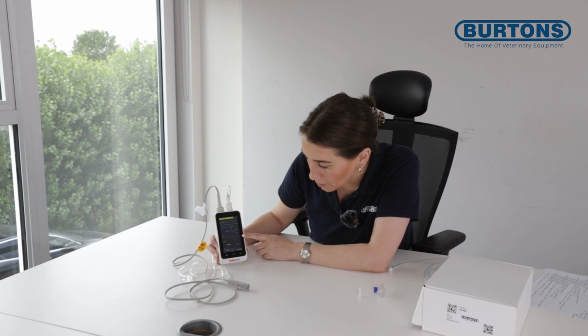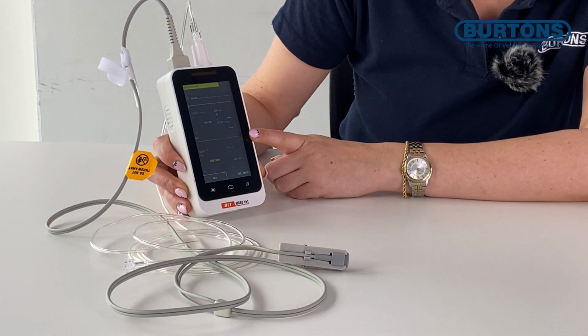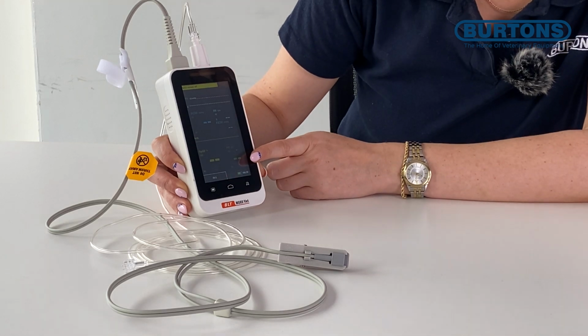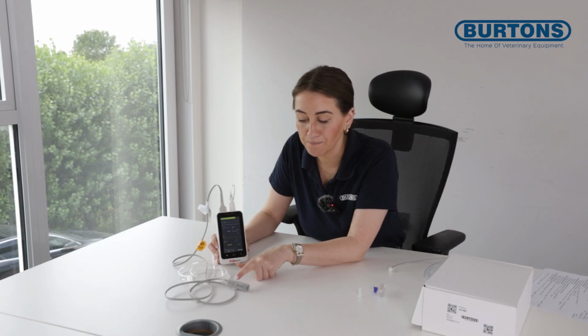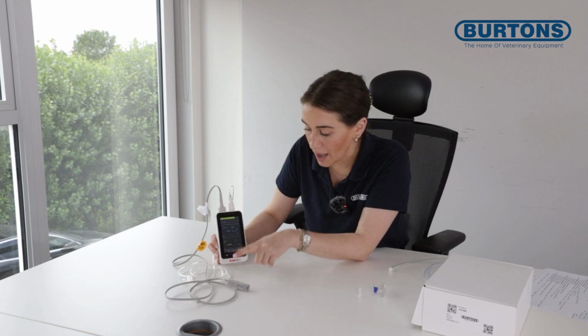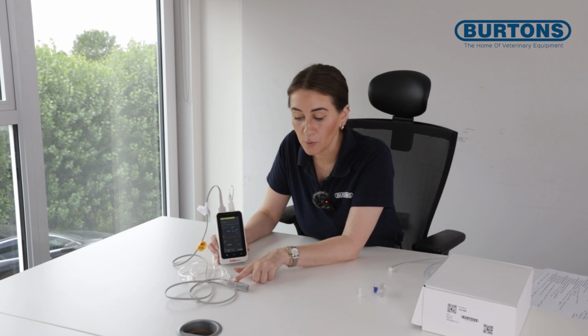So if we follow down, then we've also got what's called our pleth trace, and then we've got our SPO2. So our pleth trace is referring to the contact that the probe has with our patient, and then we will get our SPO2 percentage. So this SPO2 probe is monitoring the percentage of hemoglobin that is bound with oxygen. And we can have a patient that's desaturating, i.e. their hemoglobin is not bound with oxygen.